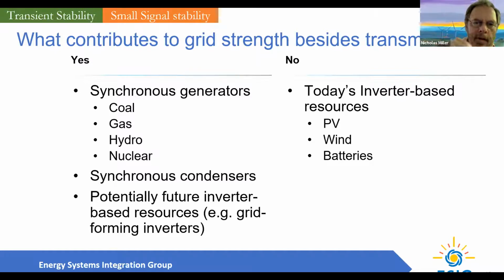But please remember, when we talk about weak grid, anything that's inverter-based does not strengthen the system. In addition to solar PV, wind, and battery energy storage systems, HVDC transmission doesn't add to system strength. And some types of voltage control devices that use inverters don't add to system strength either. So that list could actually be a little bit longer on the no side.